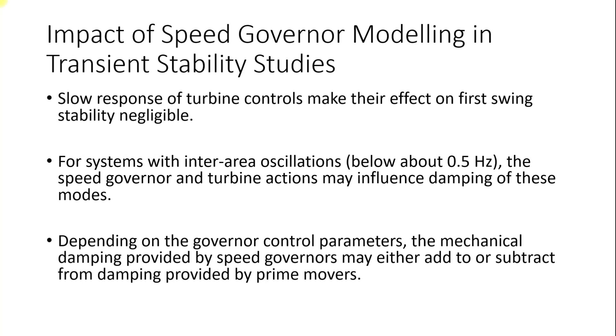Depending on the governor control parameters, the mechanical damping provided by the speed governor may either add to or subtract from the damping provided by the prime mover. For example, when one of the lines is tripped, the power on the other line was oscillating. This oscillation of power can be impacted by the governing control system because the change in power will be sensed by the governor, and the governor will respond in order to counteract this oscillation. If your governor is properly tuned, it will reduce this oscillation. But if the governor is not properly tuned, it may result in adding to the already existing oscillation and cause the oscillations to grow.